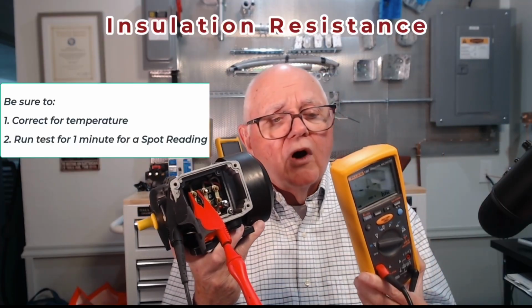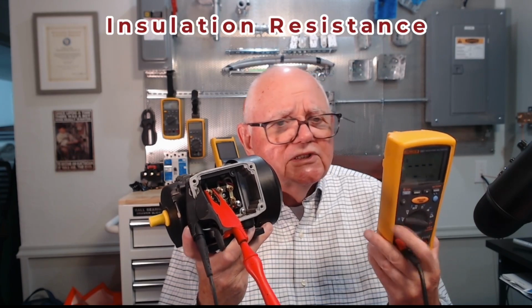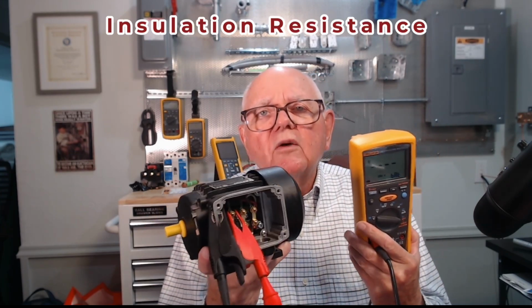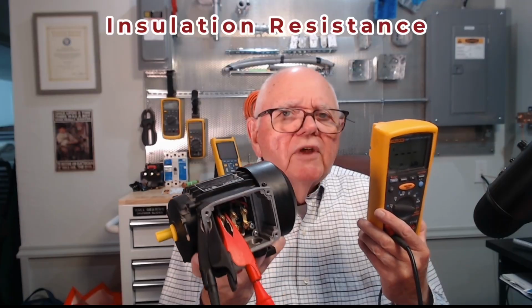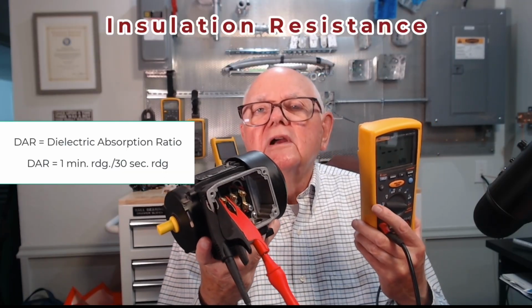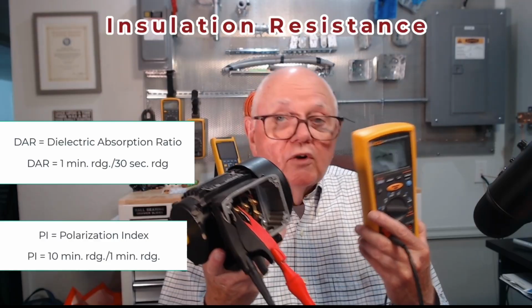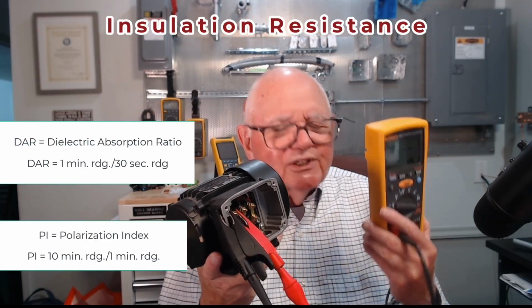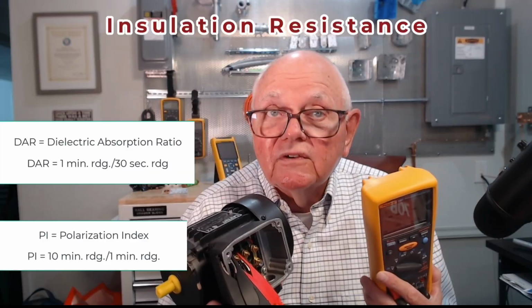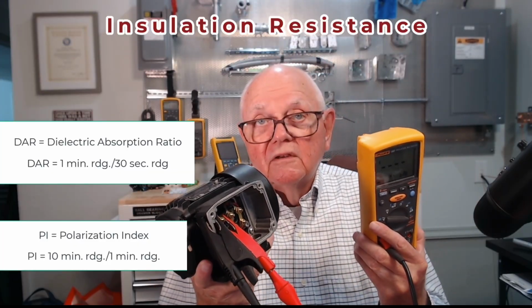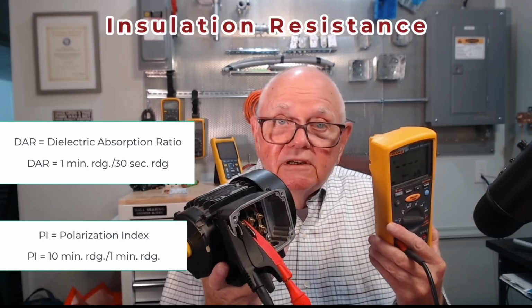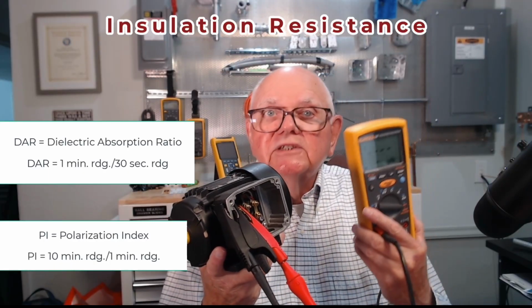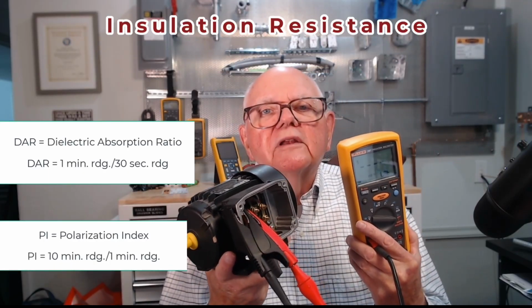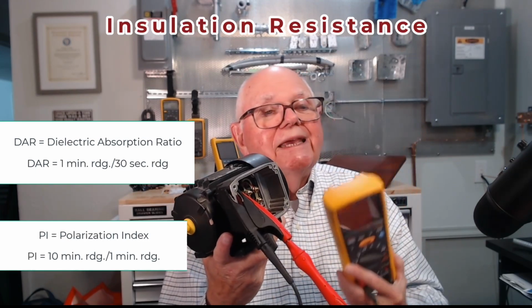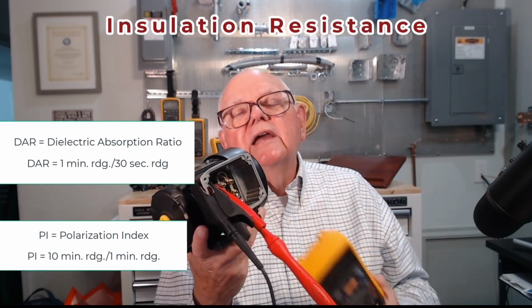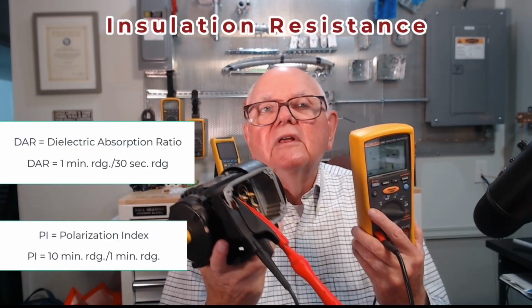Now, time-wise. Also, on this particular insulation resistance tester, it has 2 buttons that I can push. One is DAR and one is PI. The DAR is the dielectric absorption ratio. The PI is the polarization index. For the polarization index, I let my insulation resistance tester run for 10 minutes, and I take a reading at 1 minute and 10 minutes. For the dielectric absorption ratio test, I run for 1 minute, but the tester takes a reading at 30 seconds and again at 1 minute. It does the calculations for me internally in the meter and gives me a particular DAR or PI value on the face of the meter.